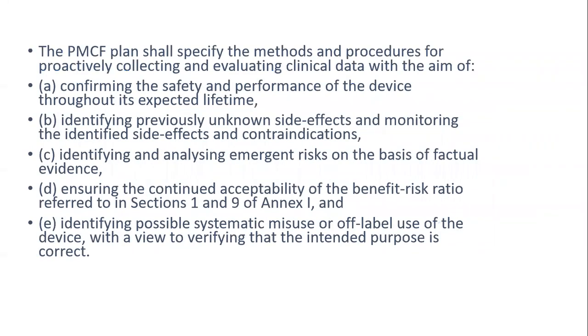The PMCF plan specifies the methods and procedures for proactively collecting and evaluating clinical data with the aim of confirming the safety and performance of the device throughout its expected lifetime. This process continues throughout the lifetime of the device. So if the product is there for 20 years, you have to update your files. It also covers identifying previously unknown side effects and monitoring the identified side effects and contraindications.